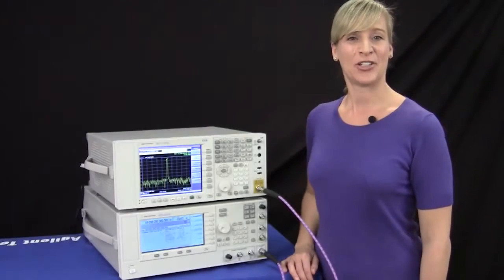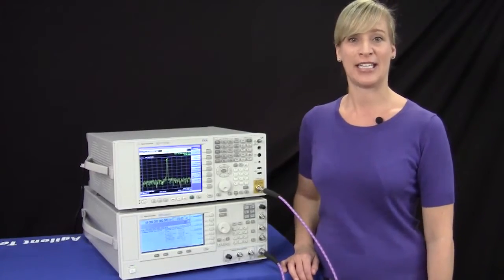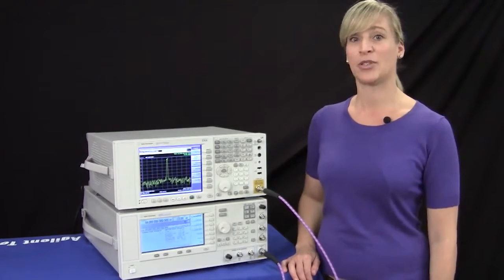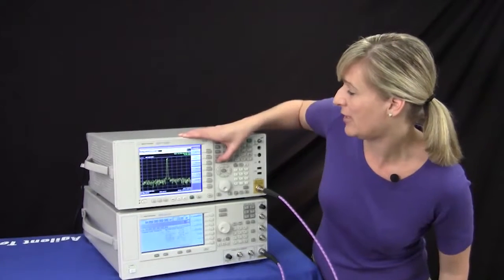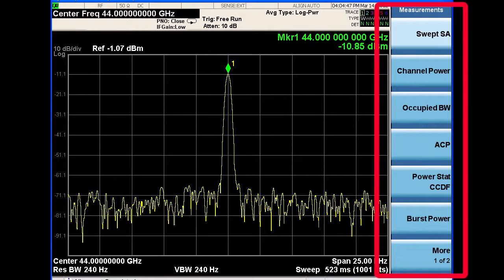For my next demonstration I'd like to highlight the measurements and applications available on the EXA. The EXA comes with standard built-in power suite measurements which are located under the measure key. You can see we have measurements such as channel power, occupied bandwidth, and adjacent channel power.